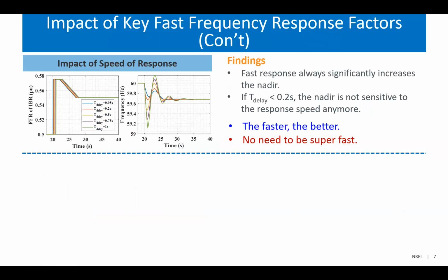First, the impact of the speed of the response. The left figure shows the FFR of the IBR with different time delays ranging from 0.05 seconds to 1 second. The right figure shows the frequency response. It is clearly seen that a faster response can always increase the nadir, but while the delay is less than 0.2 seconds, in this case, the nadir is not that sensitive at all. So it can be summarized as: the faster the better, but no need to be super fast.